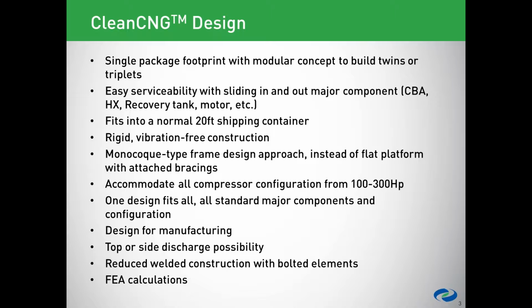Serviceability on the major components has been greatly increased with the CBA, the heat exchangers, the recovery tank, the motor, etc., all easily accessible from outside the skid to improve service of all of those components as necessary. The new package fits into a normal 20-foot shipping container for reduced shipping costs. The frame is a box frame which greatly strengthens the skid and enclosure frame, giving a lot of extra rigidity, and that has greatly helped to reduce the vibration of the package.